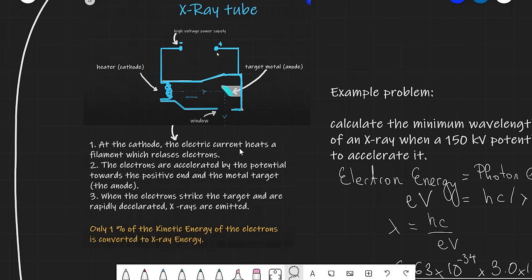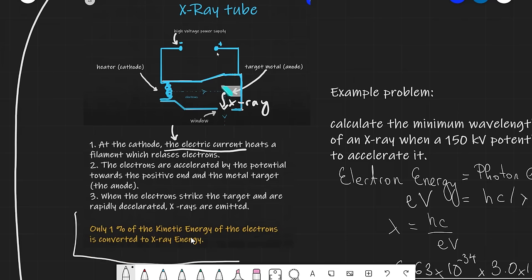The basic idea is that a very high electric current heats up the filament which releases electrons. The electrons fly towards the target and once they hit the target they emit x-rays. This process is known as Bremsstrahlung in German. This process is very inefficient — only one percent of the kinetic energy of the electrons is converted into x-ray energy.